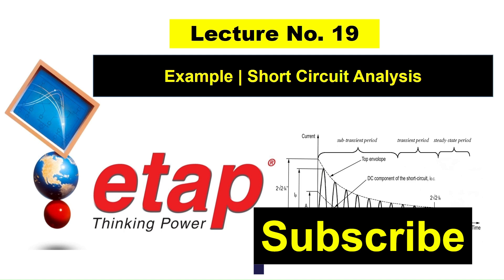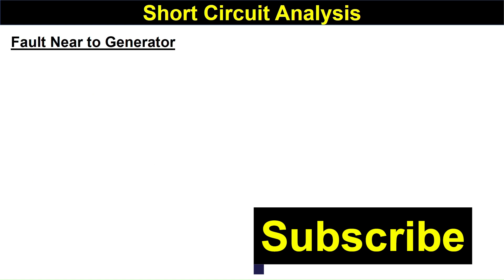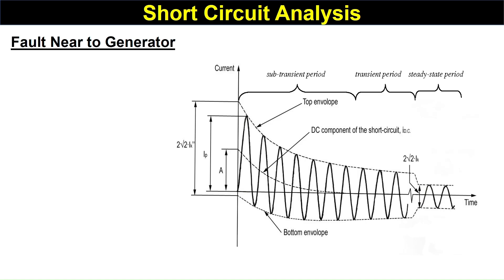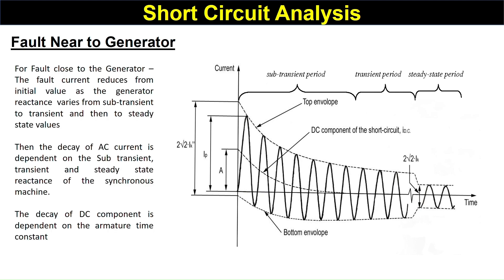First, you should know about fault current near to the generator. If the fault occurs near to the generator, the graph is asymmetrical because the fault current reduces from its initial value as the generator reactance varies from sub-transient to transient and then to steady state. There are three periods: the sub-transient period, the transient period, and the steady state period.